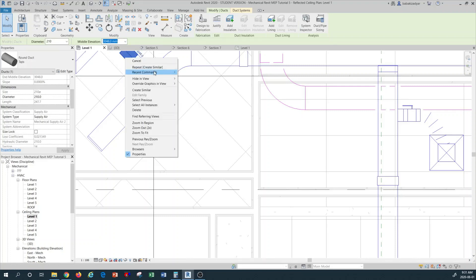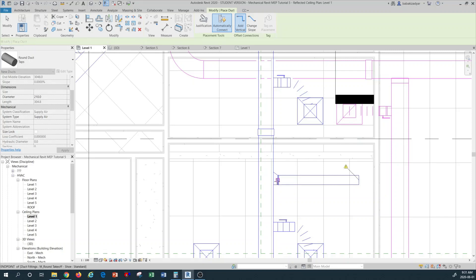One other thing I want to show you is fitting changes — how to change your fitting for duct connection to your main branches. I'm going to draw a little duct here. I grab one of my round branch ductwork, left click, and right click to Create Similar. This grabs the properties of that duct including its size, shape, and system — whether it's supply or return. I left click, drag this all the way here, left click to stop, and I have a new branch with a new fitting type that is different from the others.